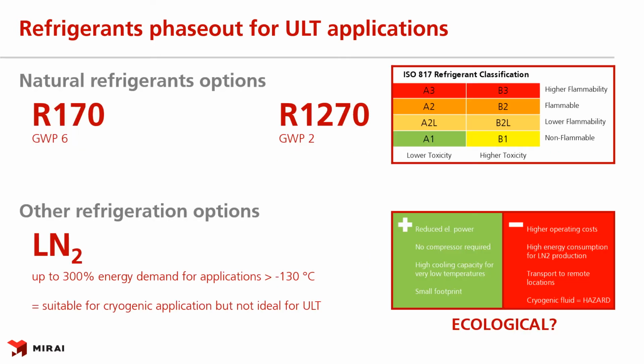What are the natural refrigerant options for ultra-low temperatures? One of them is ethane and propylene working in cascade, but both are A3 classified refrigerants. That means higher flammability, which brings the burden of strict safety measures and potential risk. Another frequently used solution for ULT refrigeration is liquid nitrogen. Liquid nitrogen is great for cryogenic applications, but has questionable benefits when it comes to ultra-low temperature applications.